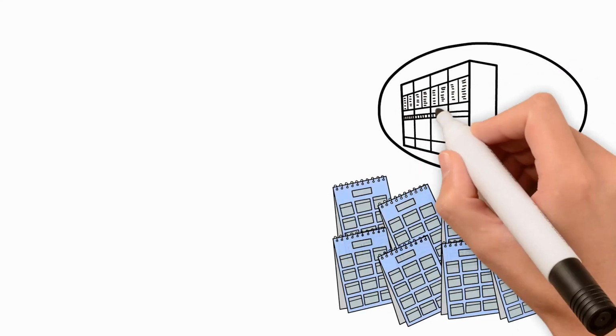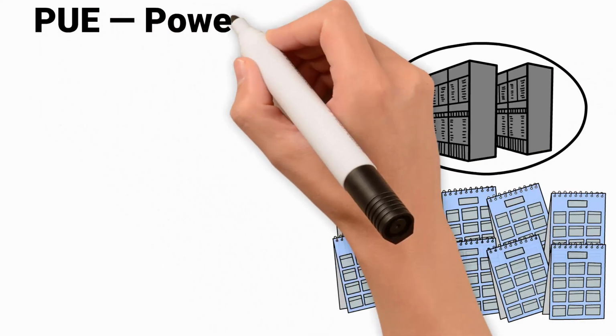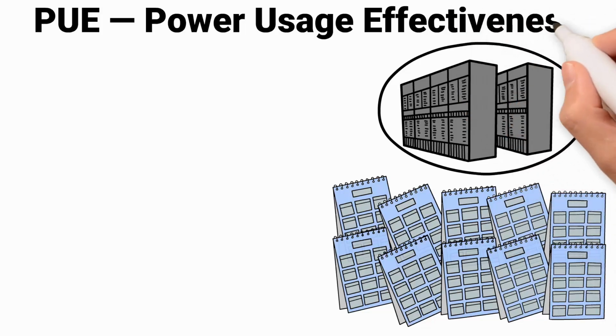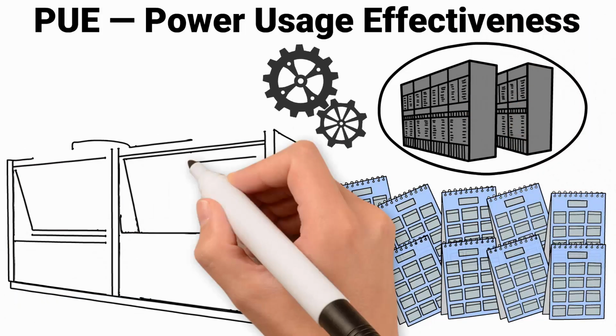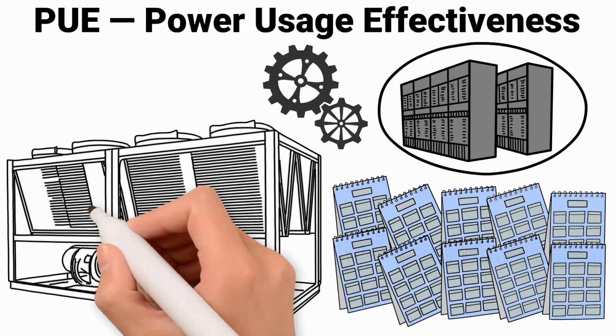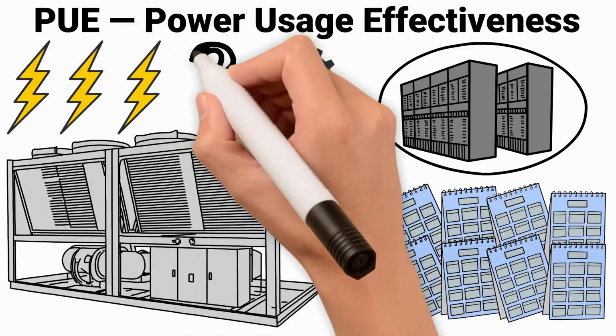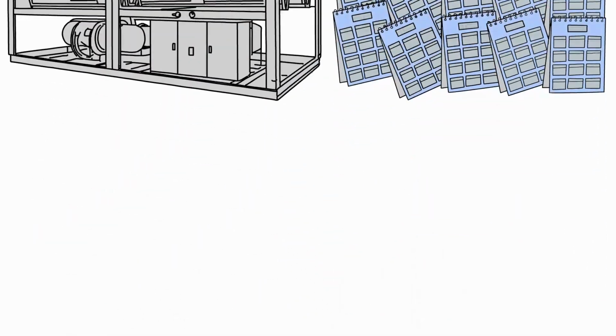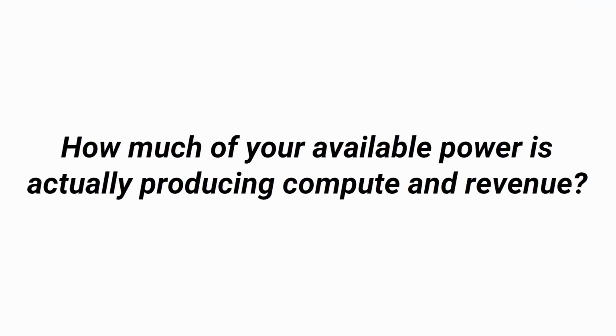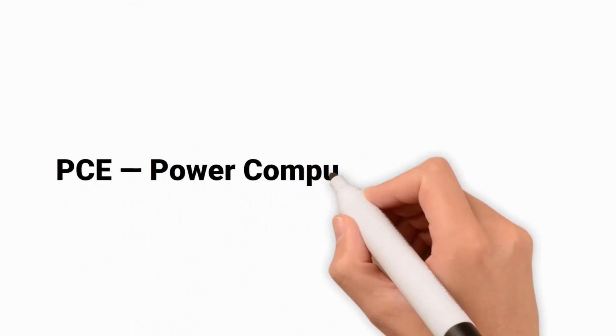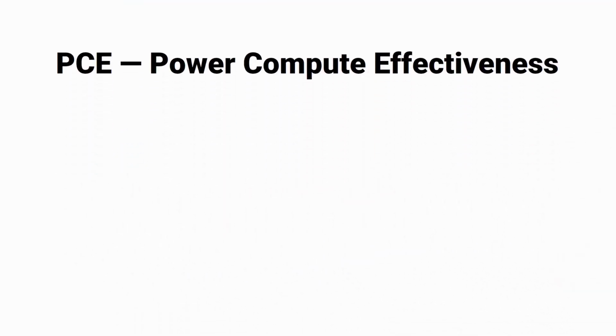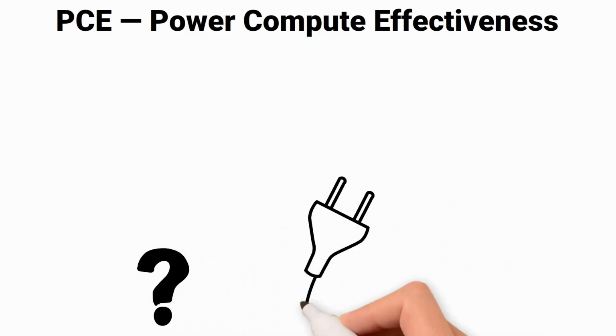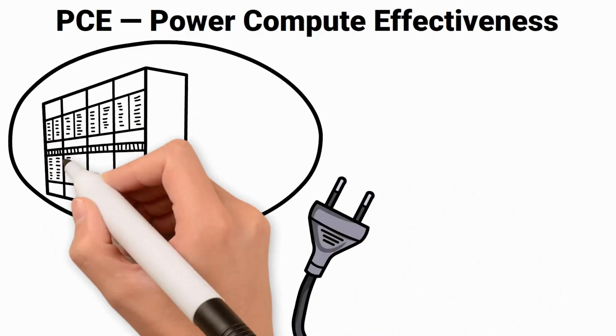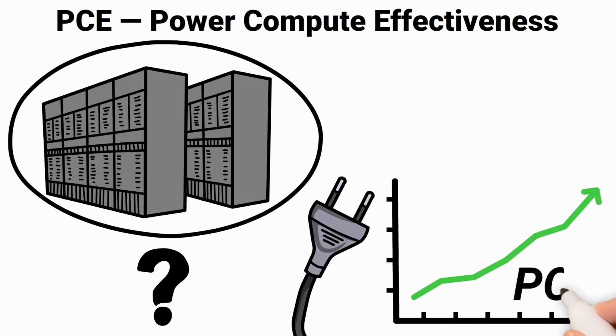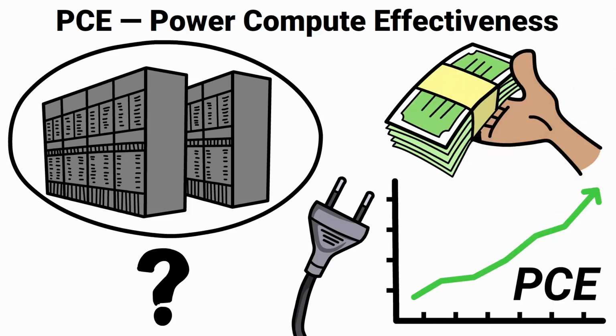For years, the data industry has relied on PUE, power usage effectiveness, to measure efficiency. And while PUE tells us how well cooling systems use energy, it doesn't answer the most important question. How much of your available power is actually producing compute and revenue? That's where PCE, power compute effectiveness, comes in. PCE measures how much of your provisioned power is directly driving IT load. The higher the PCE, the more of your capacity is monetized.